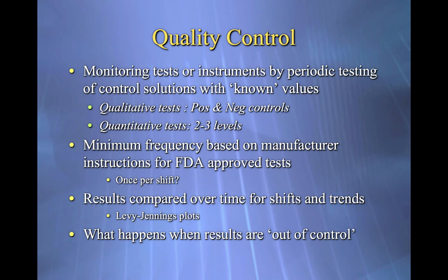an out of control result and you have failed your quality control testing procedure at the beginning of a run, you're not going to test any patient samples, you're out of control. But you also need to go back, once you are back in control, you've tweaked the assay, you've rerun controls, and I'm now in control, you should really go back and try and test all of the samples from the last point you were in control to when you went out of control.